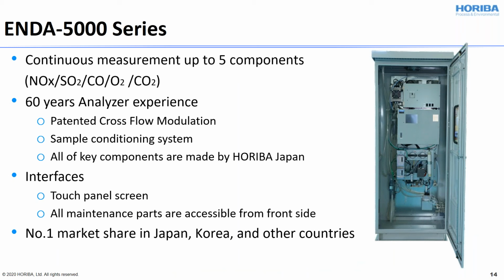Here is the outline of ENDA-5000 features. It can measure up to 5 components at the same time, including NOx, SO2, CO, O2, and CO2. HORIBA has 60 years of analyzer experience. Based on that experience, HORIBA developed the patented cross-flow modulation, which gives great durability of analyzers and stable performance. I will explain that later. And also the sample conditioning system is well designed for each application, especially since incinerator application is one of the difficult applications to deal with.